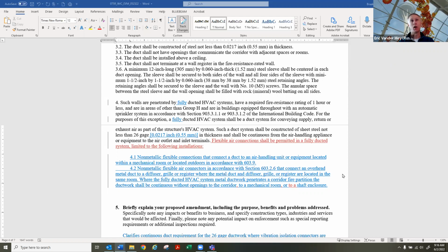So, right. You are allowed to penetrate the demising wall between dwelling units, and you have several options of how you do that. The most common would be an option to use this exception, as long as you had a fully continuous metal duct, you could penetrate that and provide an open duct between that. You're already allowed to do that with the special sleeve option in item 3 above, or you could provide fire dampers if you chose, correct? Okay, thanks, Eric.